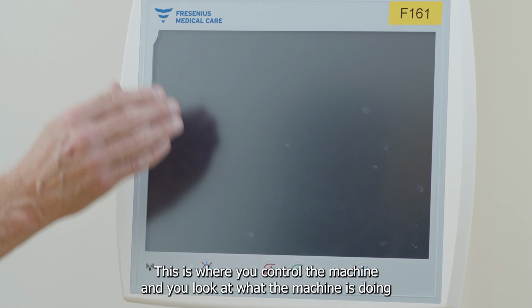On this side of the machine, you can see the monitor tilts backwards and tilts forward. It has some movement like that, so you can view the monitor when you're dialyzing. You can also access the drip stand. Your bags of saline will go. To move the drip stand up and down, hold that bottom section there and push that ring upwards, and it allows you to push the dialyzer drip stand up and down. To bring it back down, you do the same thing, hold the bottom, push that ring upwards, and it allows you to bring that back down.